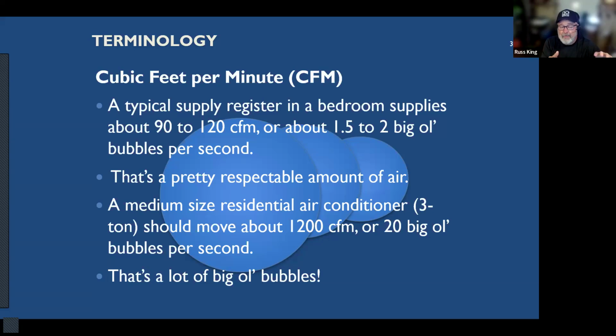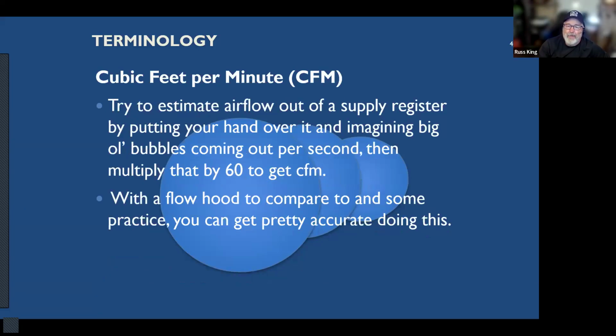Now remember, I said one of the things that affects an air conditioner's ability to cool is how much air is blowing across a coil. So instead of 2,000, you might only be getting 1,700 or 1,600. And now it starts to affect the air conditioner's ability to cool and its efficiency. It's a double whammy. We'll talk a little bit more about that.